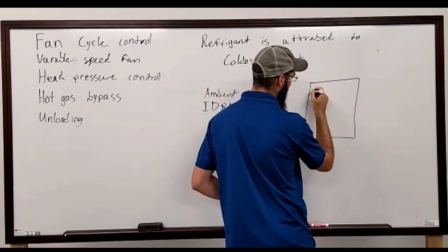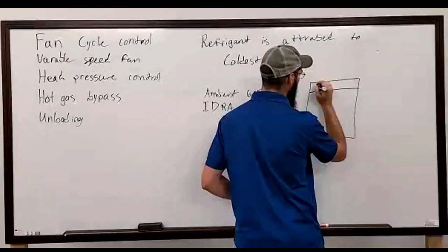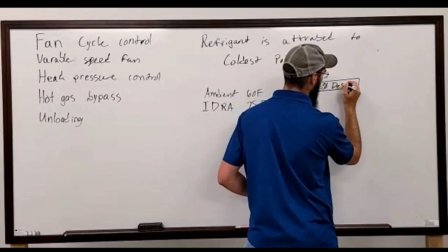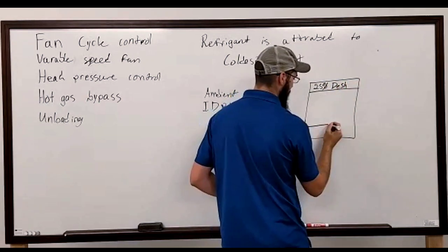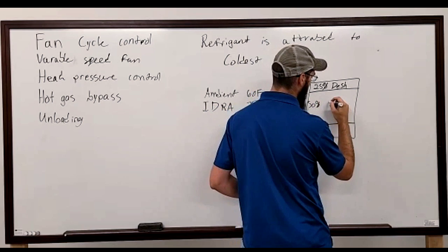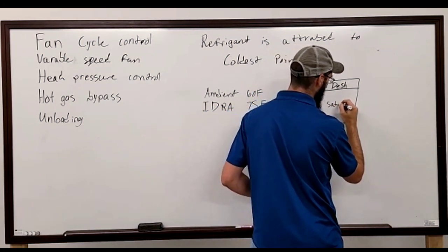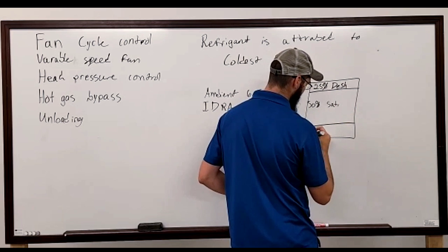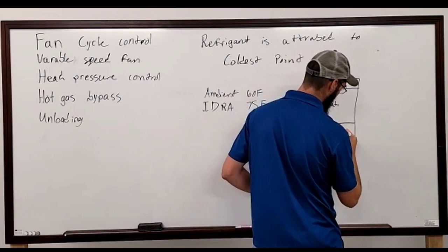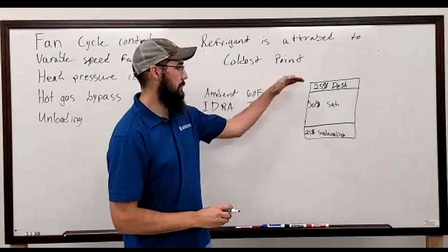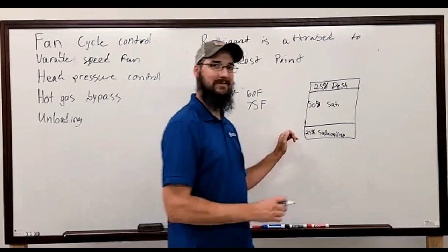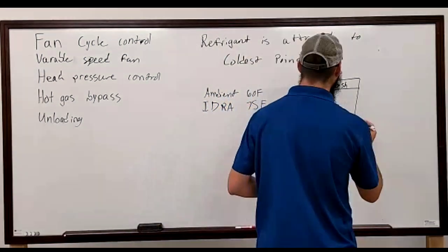Well, in this particular case, what will happen, specifically on a condenser coil, is your top, we'll say, quarter, top 25%, is de-superheating. The middle 50% of your coil is typically going to be saturated. And then the bottom 25% is your subcool. Right? This is a typical coil function. So let it follow. Trying to make sure we don't have any questions.